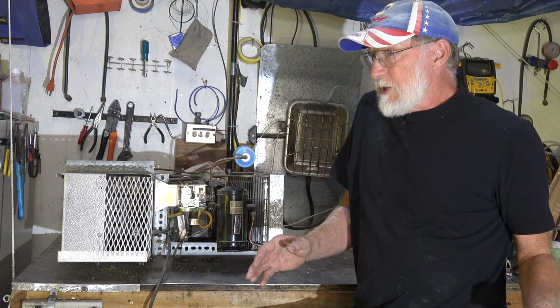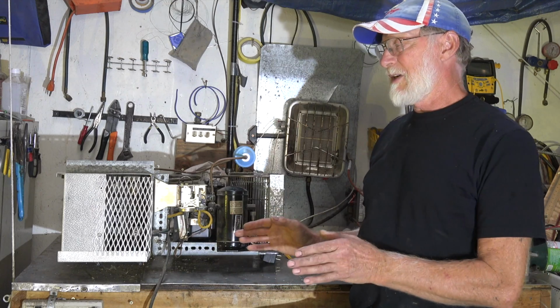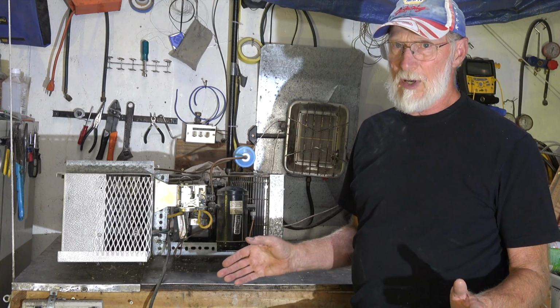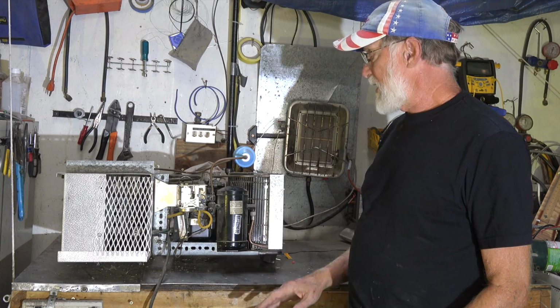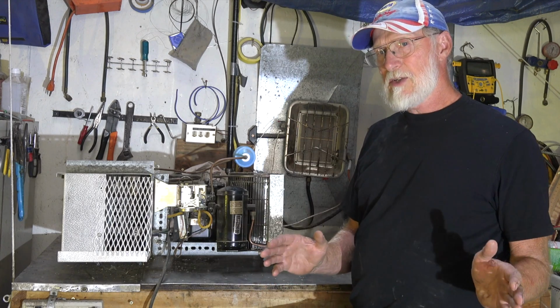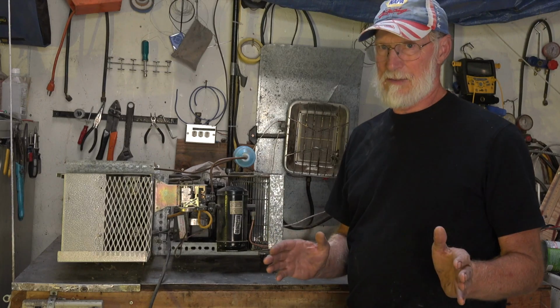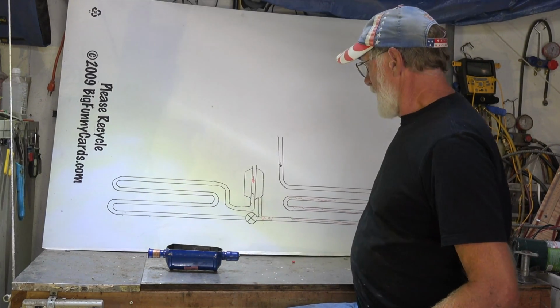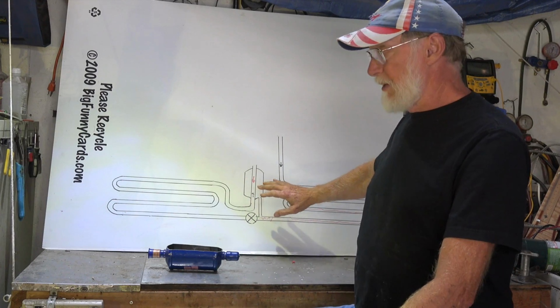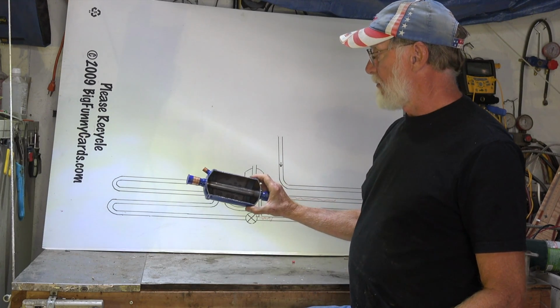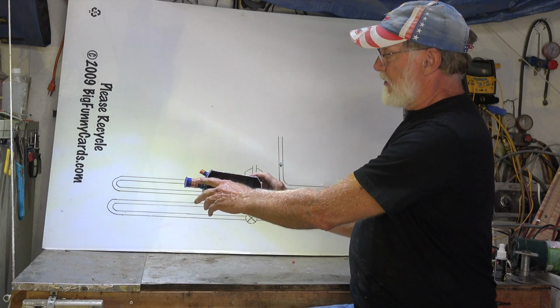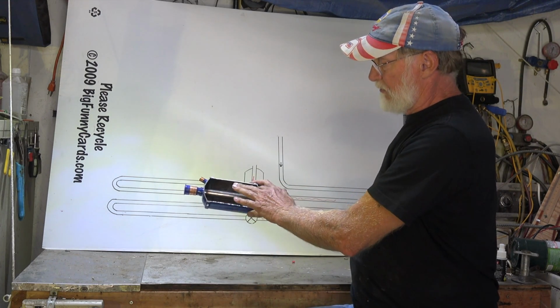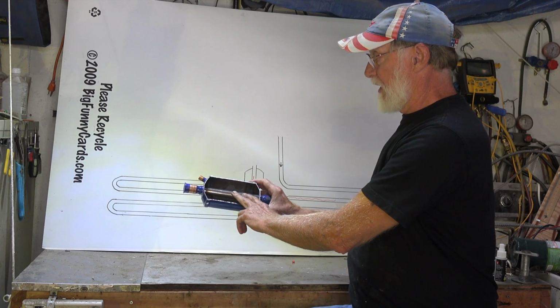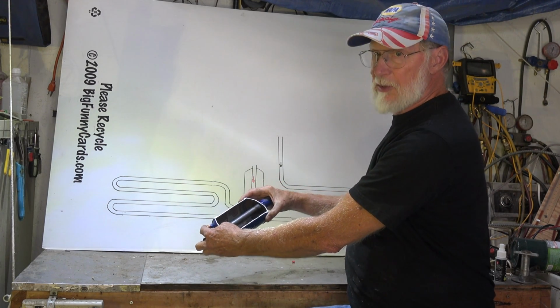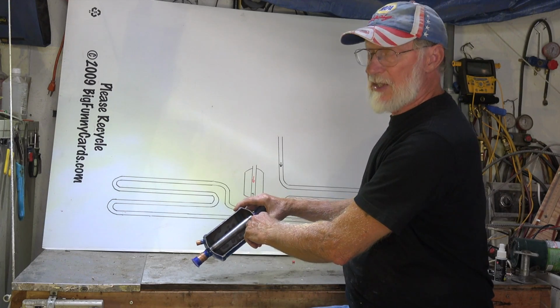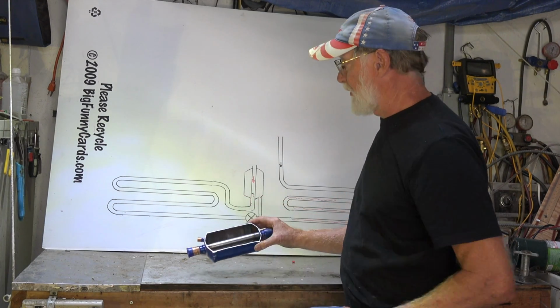In some ways that's similar to a charge compensator, but there are differences, certainly in operation. So let's take a look at the charge compensator and what it does. Now, here I've got this drawing. I used this before in an earlier video. And here's the charge compensator. It's a pretty simple device. The suction line goes through here, suction slash discharge line. It gets cold, and liquid refrigerant comes in here and fills this up because of the cold refrigerant coming through.